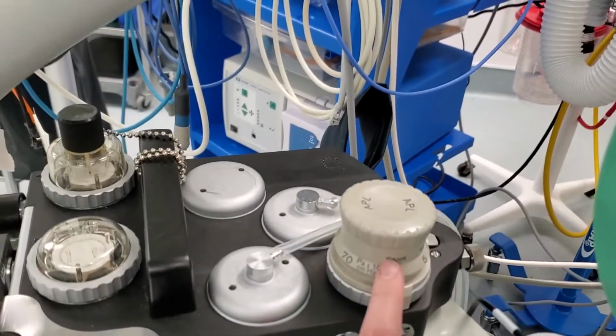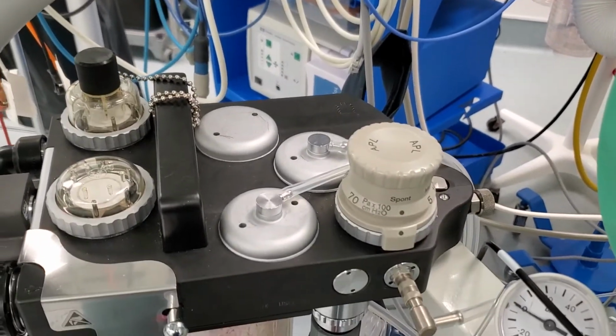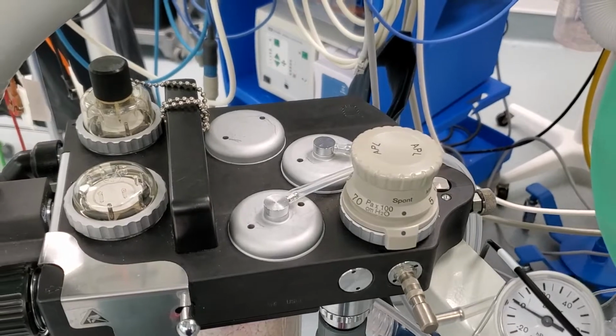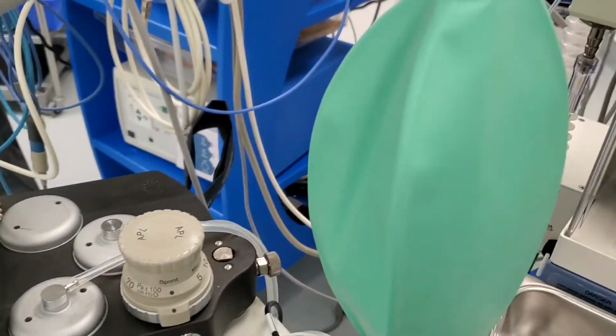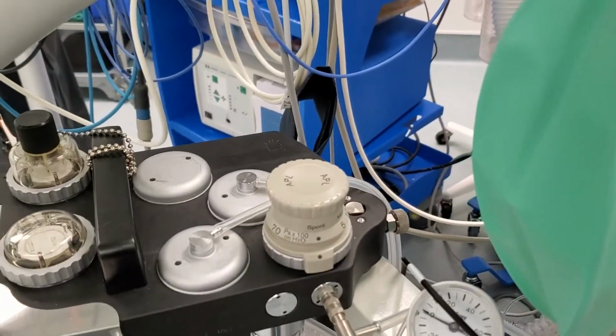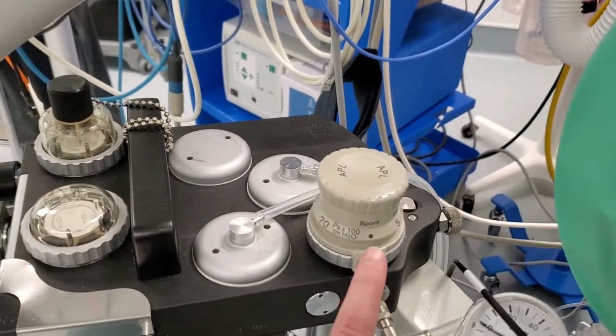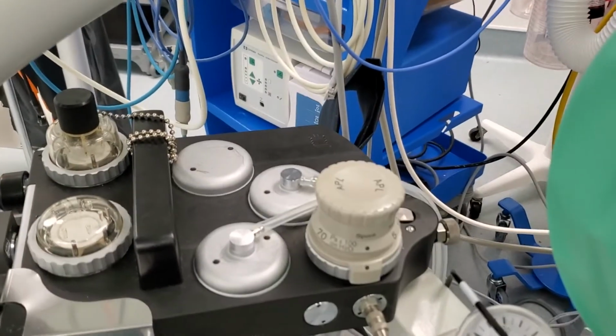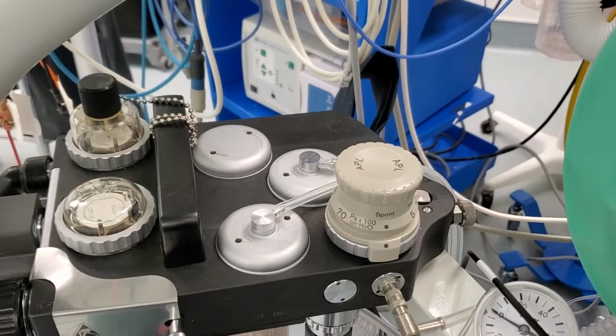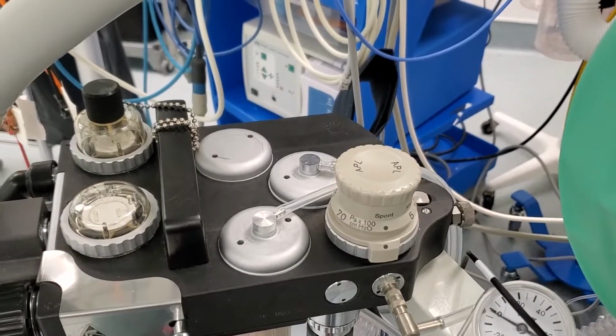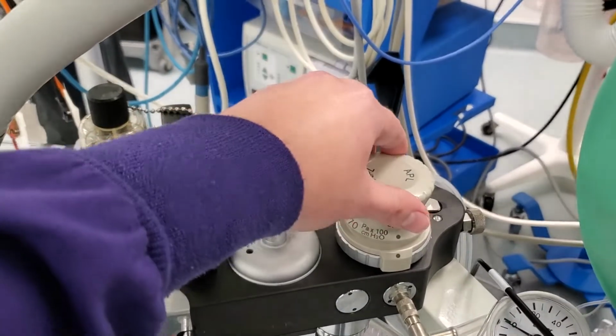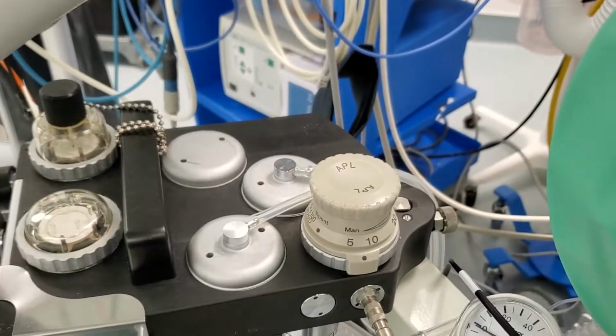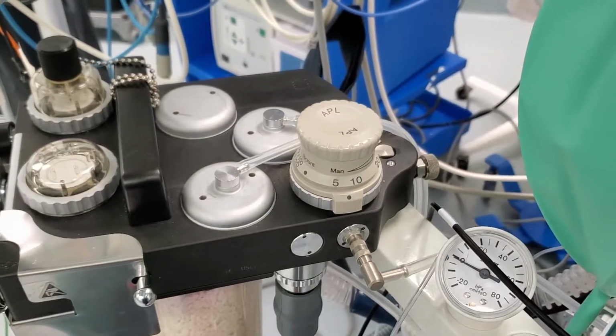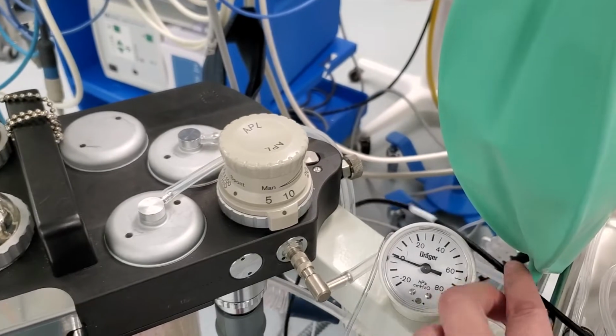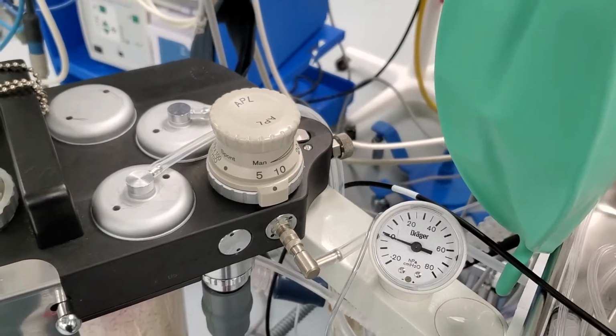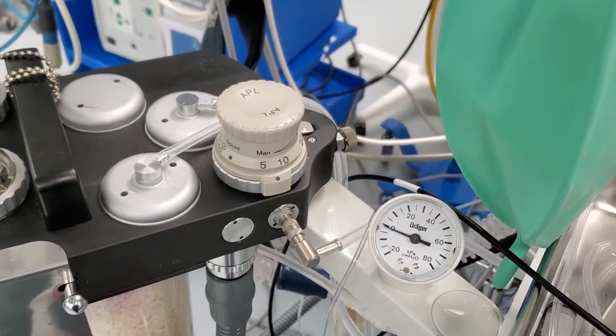Basically the APL valve is the adjustable pressure limiting valve, and this will help direct flow into the breathing bag for manual and spontaneous breathing. So during spontaneous breathing, we don't want any resistance. We want the patient to get 100% oxygen, so we don't want rebreathing to occur. And once the patient goes off to sleep, we can close this valve. It depends on how much of a leak you have when you're bag masking, and this pressure gauge will correspond to the pressures that the patient is getting when you're bagging.